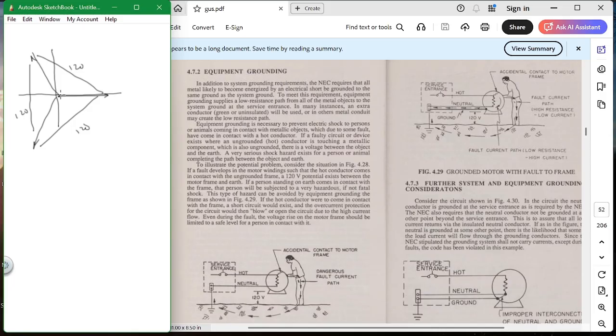And they have a neutral, and what they do is put a light right here, and a light right there. If you walk into a plant and all three lights are up in a little tattle box over your power system, and those three lights are all kind of dim, there's no problem. If one of those lights is out, it means you have a ground at that point — here, here, or here.